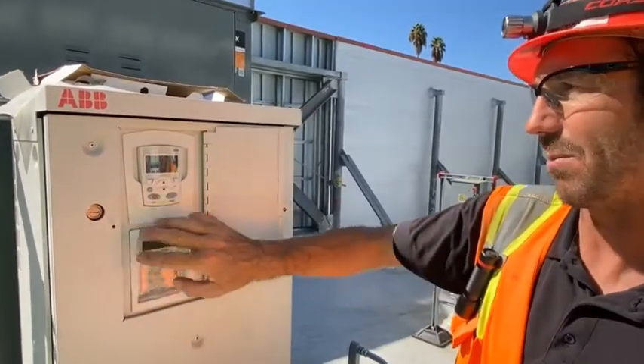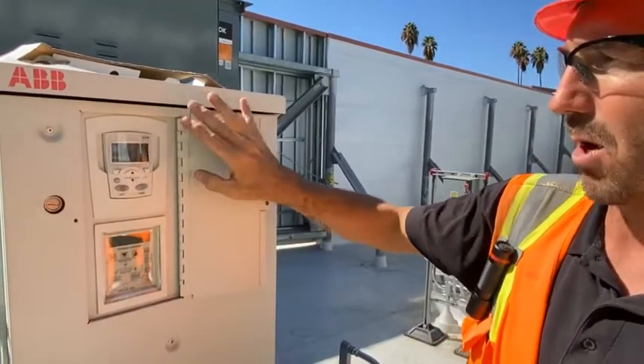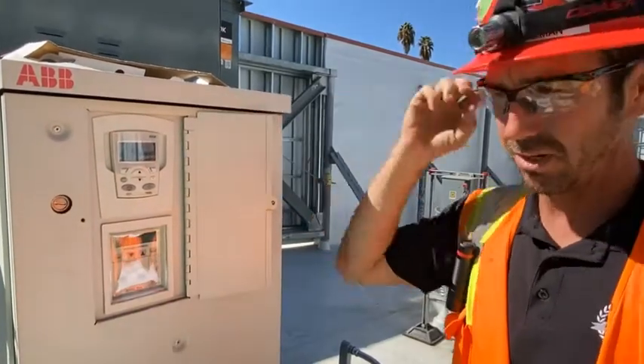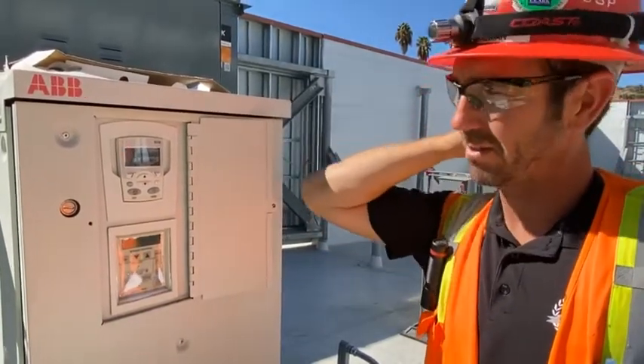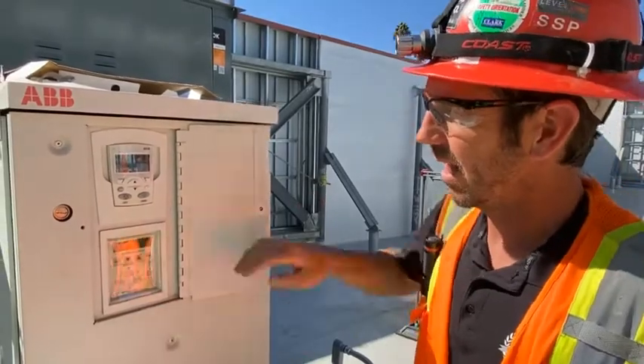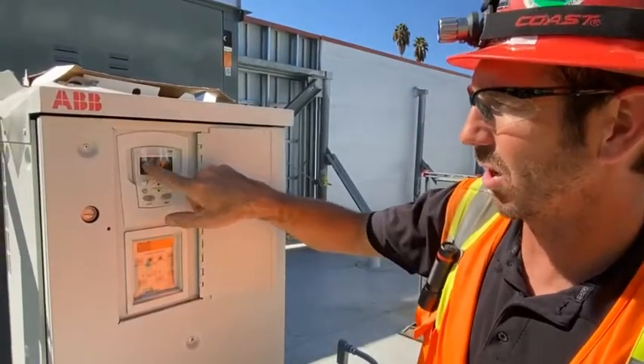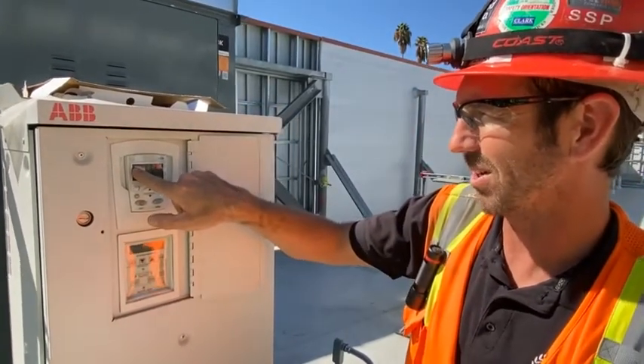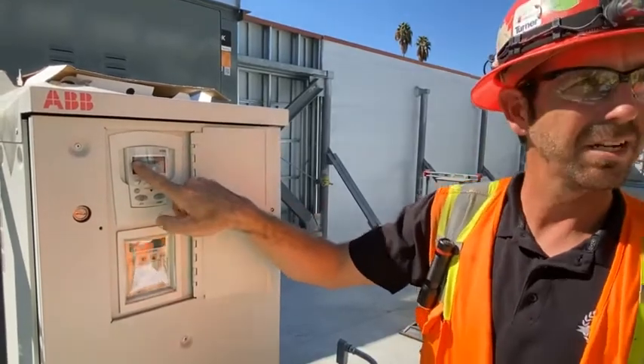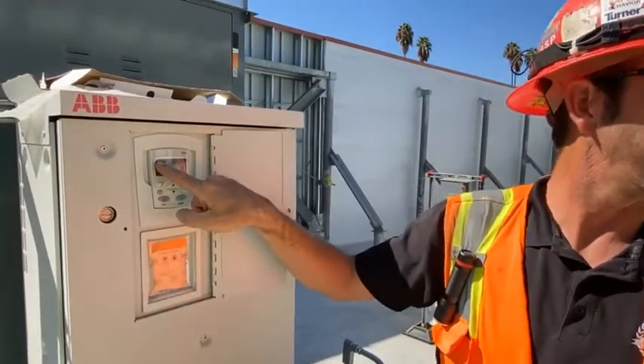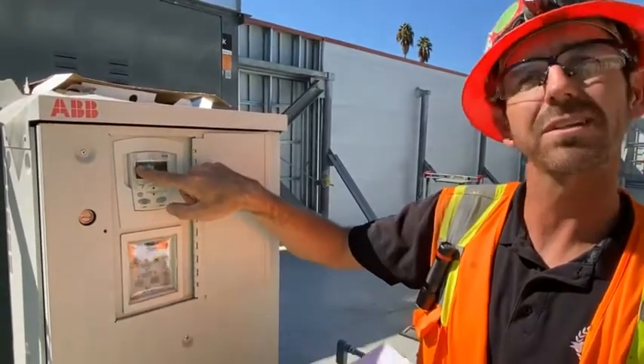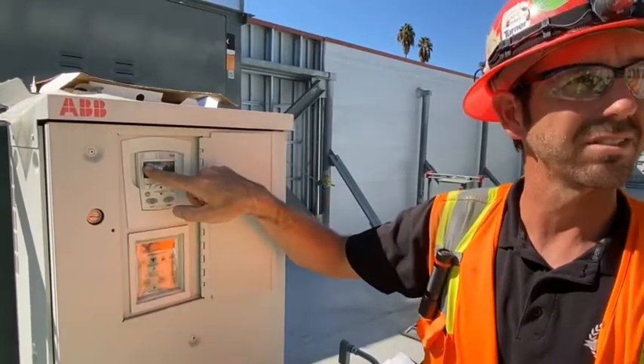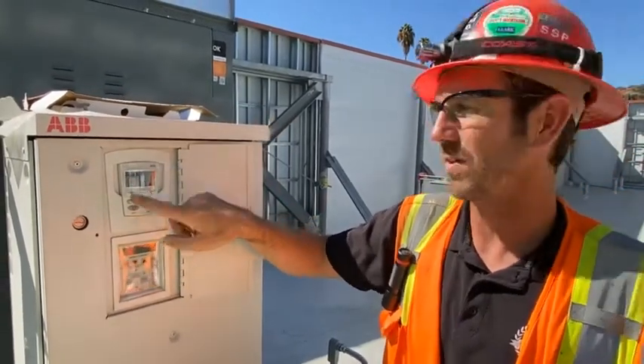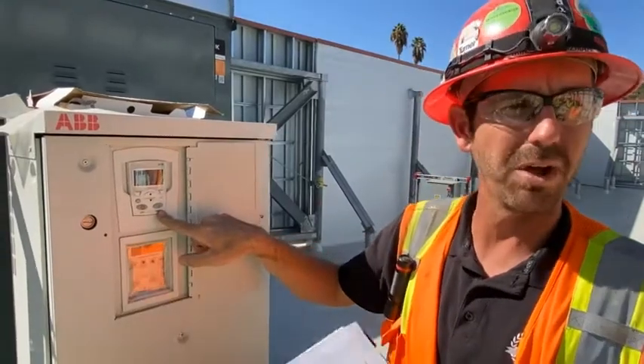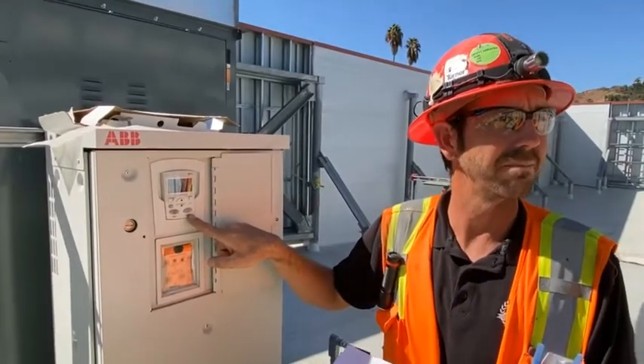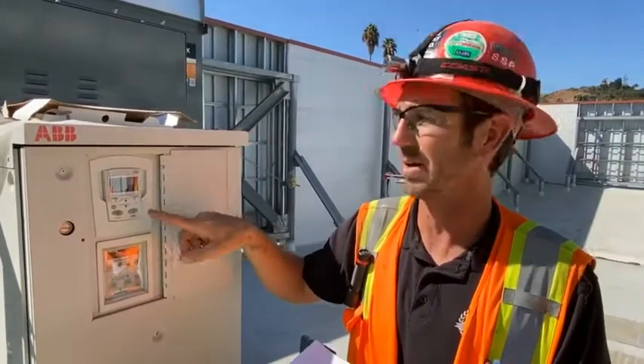Done with this keypad, we're moving up to the drive keypad. The most important thing is that when you guys come up here, you do an inspection on the keypad, and we want to make sure that this unit always stays in auto. In the top left corner, you can see it says auto. That's going to be able to turn this fan on and off, okay? This fan is only being turned on and off through the Ansel system, okay? So if you came up here and pressed hand, the fan will run for an indefinite amount of time, okay? We want it to be in the auto mode.